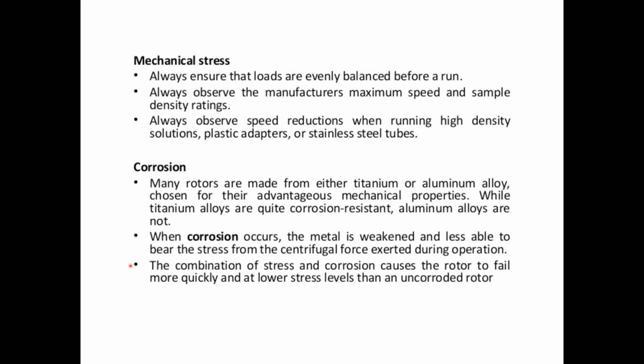The rotors have to be taken care of for corrosion. Many rotors are made of titanium and aluminum. Aluminium is not corrosion resistant, whereas titanium is. And when corrosion occurs, this weakens the metal surface, and the stress that is applied by 100,000 G centrifugations is tremendous. So be careful. And if you see that the rotor looks damaged from outside, don't use it, and consult immediately with more experienced researchers and technicians in the lab.